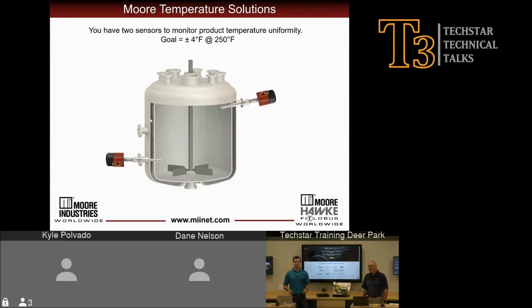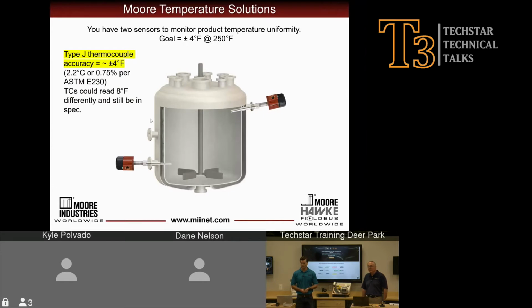So in this application on this slide here, we've got a process where the production team has come to us and told us, hey, we have a goal of being within plus or minus 4 degrees Fahrenheit in order to have a successful process. So we want to measure this vessel uniformly. So we're going to have 2 temperature sensors implemented here. And we know that one of the American standards we use for thermocouples tells us that a type J thermocouple out of the box in perfect operating conditions has an uncertainty of plus or minus 4 degrees Fahrenheit.